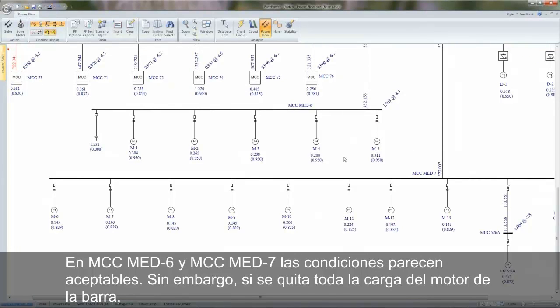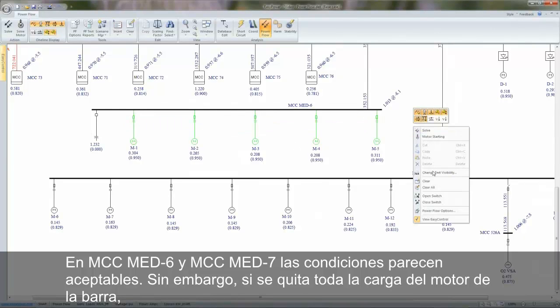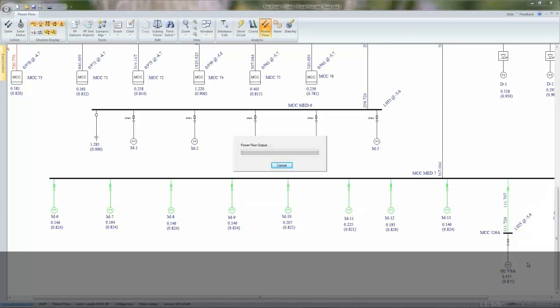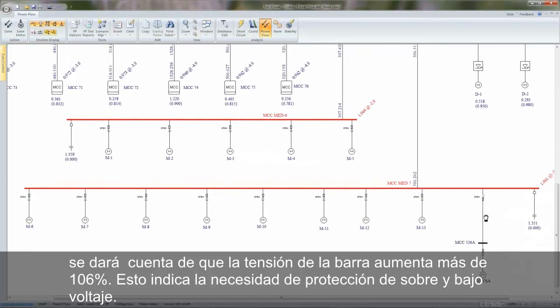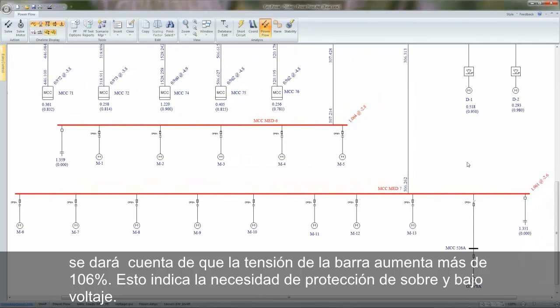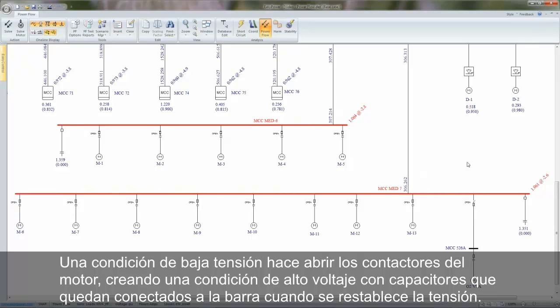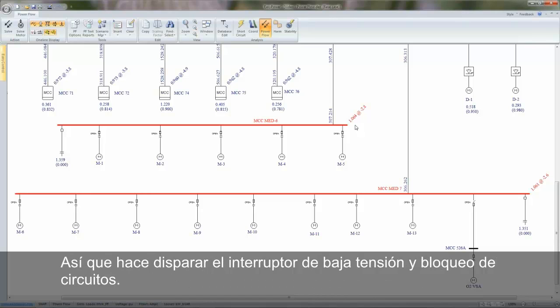However, if you remove all the motor load on the bus, you'll notice that the bus voltage increases over 106%. This indicates a need for over and under voltage protection. A low voltage condition drops motor contactors, creating a high voltage condition with capacitors left on the bus from when the voltage is restored. So apply a low voltage trip and lockout of the banks.